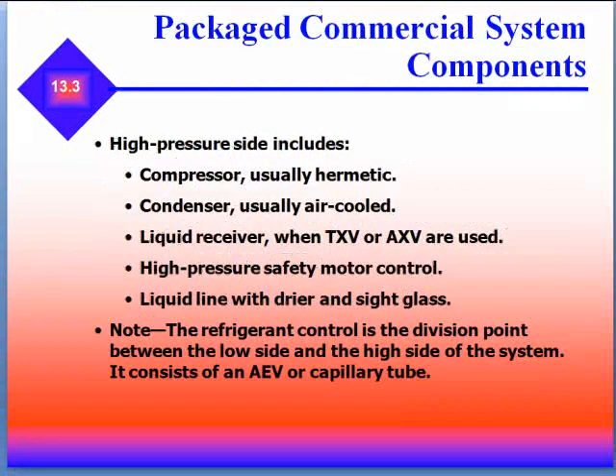The high pressure side includes compressors — usually hermetic — condensers that are air cooled, liquid receivers when a TXV or AXV is used, high pressure safety motor controls, and a liquid line with dryer and sight glass.